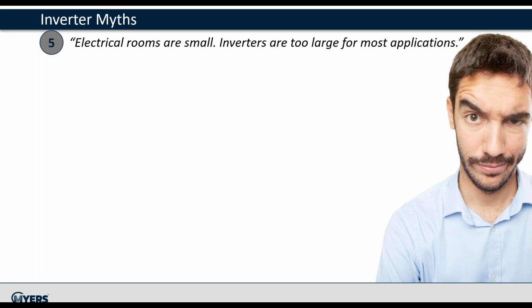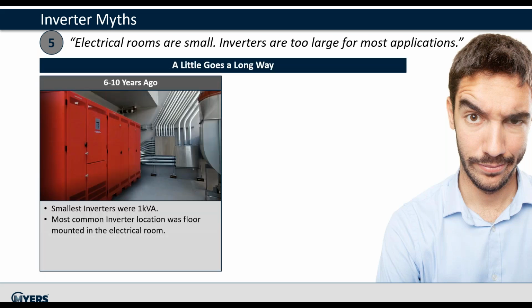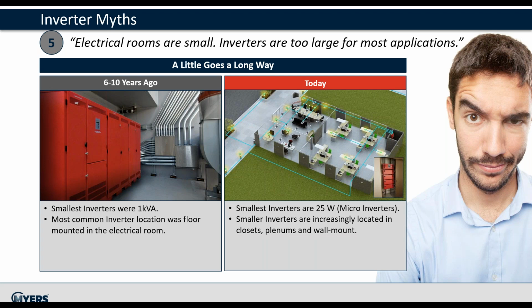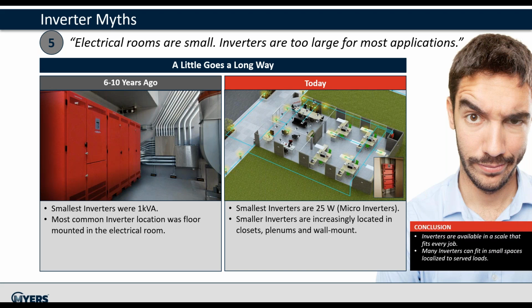Inverters are too large for most applications. In the past 5 to 10 years, LED power requirements dropped, as well as inverter power sizes. For applications up to 3 kilowatts, most inverters are wall-mounted versus cabinet structures and occupy a much smaller wall footprint. Microinverters, which are less than 100 watts, have superior mounting flexibility and can be mounted in plenums, ceilings, and on walls. Summary is that there's a variety of sizes of small inverters available to choose from, so the same space can have one or multiple inverters accommodating the emergency lighting needs, as well as the space that's available.